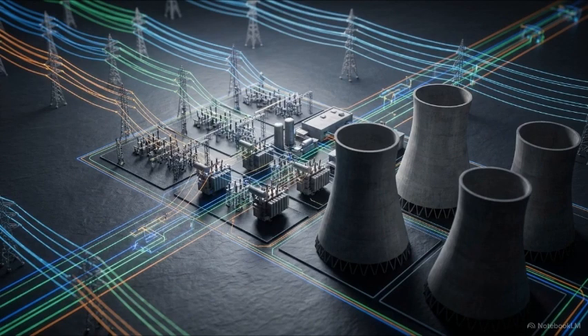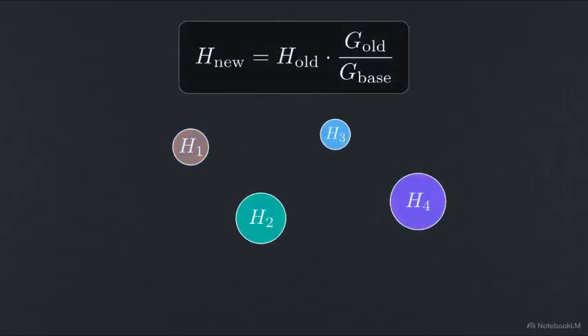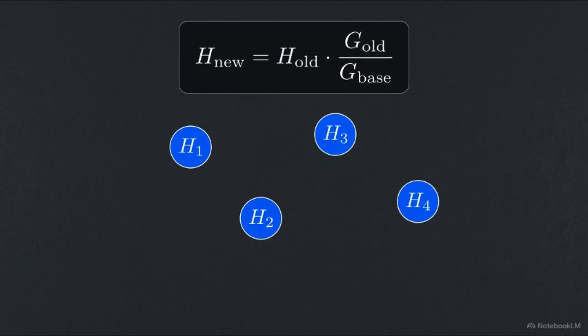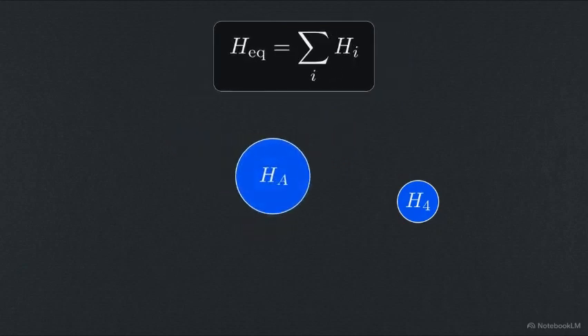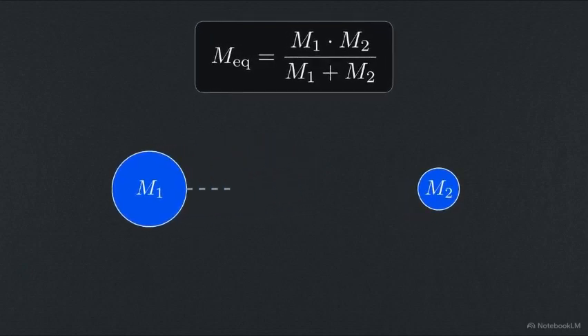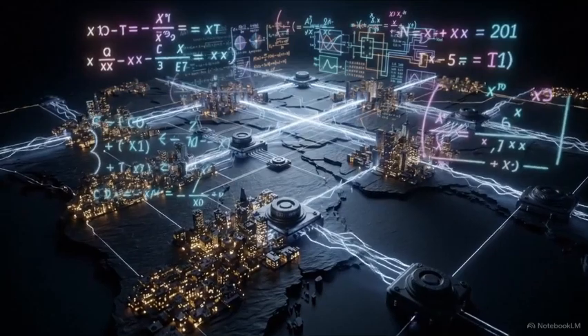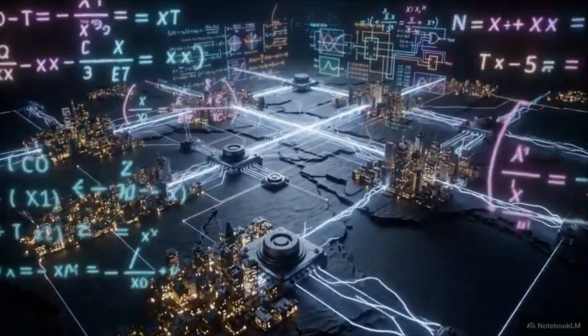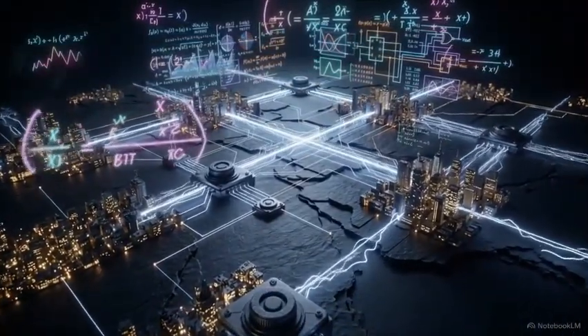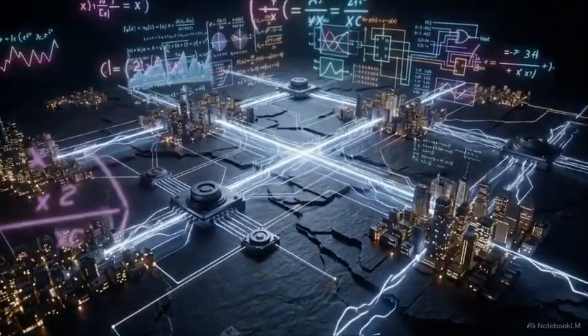Fortunately, individual turbines do not face these disturbances alone. A power plant is part of a larger grid, where multiple units share the load. To analyze multiple generators, their inertia constants are converted to a common base MVA. Coherent units in the same station directly sum their inertia into a single entity. Separate stations on tie lines act non-coherently. Their reduced mass system divides their momentum's product by its sum. The vast, decentralized layout of a modern grid uses interconnected mathematical counterweights to dilute local disturbances across hundreds of miles.